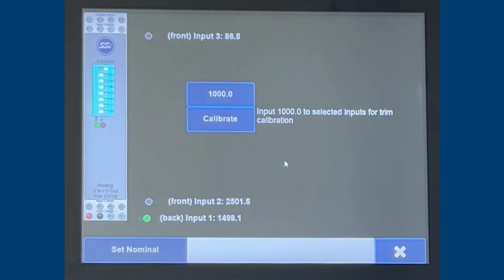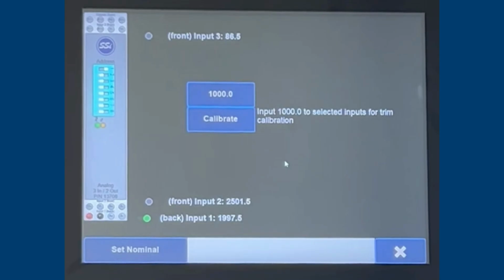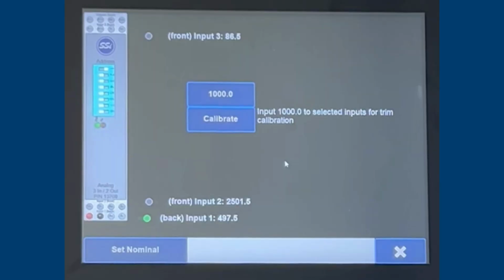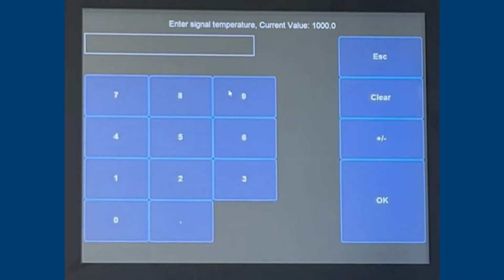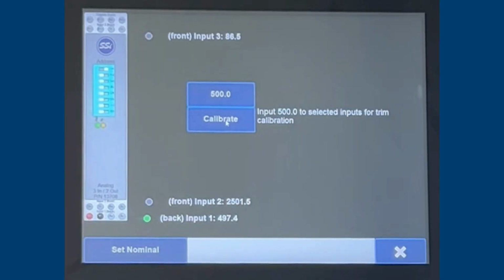Sourcing 1,500 degrees and we are reading 1,498. Sourcing 2,000 degrees and we are measuring 1,997. Sourcing 500 degrees and we're reading 497. If necessary, another trim adjust may be performed if we wanted to do lower or higher temperatures. We would then just edit the temperature being sourced in and then select the Calibrate button.